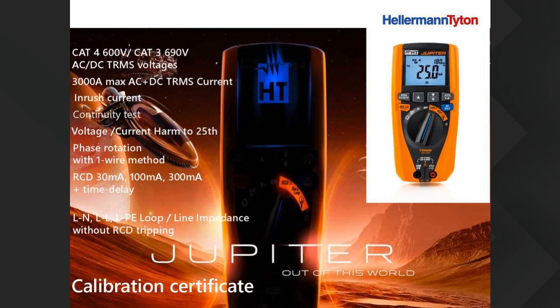So this meter is designed with a 2-wire test that allows you to test between live and neutral, live and earth, and live to live as well, where a lot of PSC loop testers or prospective short circuit current and loop testers aren't allowed to do that. And what's nice about this tester, if you test from a socket, it will not trip your earth leakage, which is a very, very nice feature, where a lot of conventional PSC loop testers will trip your earth leakage if you test from a plug socket point.